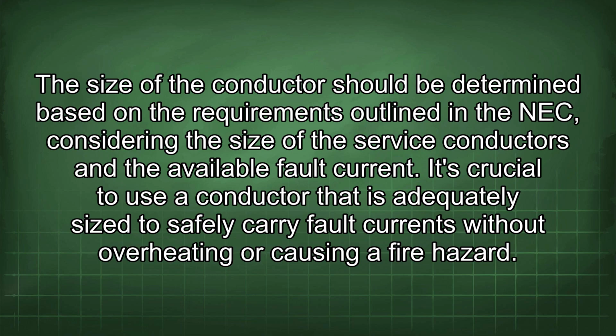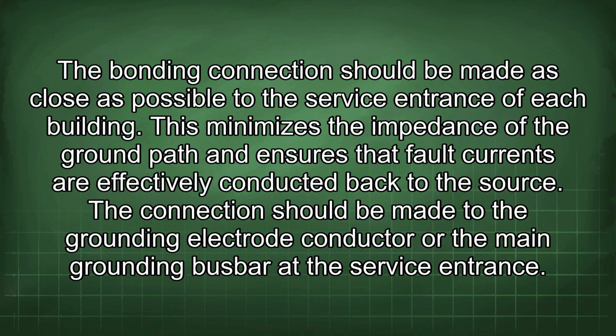It's crucial to use a conductor that is adequately sized to safely carry fault currents without overheating or causing a fire hazard. The bonding connection should be made as close as possible to the service entrance of each building. This minimizes the impedance of the ground path and ensures that fault currents are effectively conducted back to the source. The connection should be made to the grounding electrode conductor or the main grounding busbar at the service entrance.